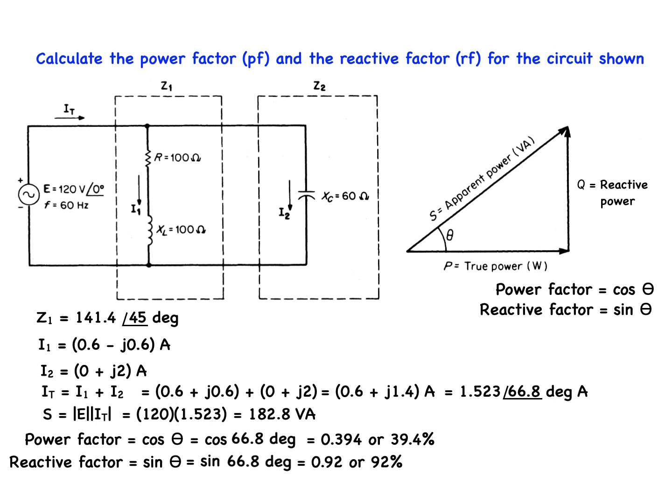Inductive loads have a lagging power factor. Capacitive loads have a leading power factor. The value of the power factor is expressed either as a decimal or as a percentage. This value is always less than 1.0 or less than 100%. The majority of industrial loads, such as motors and air conditioners, are inductive, lagging power factor. Thus, power engineers often refer to capacitors or capacitive loads as sources of reactive power.